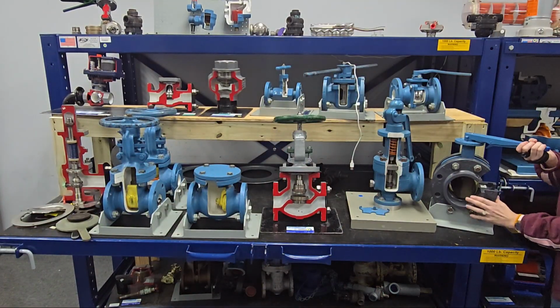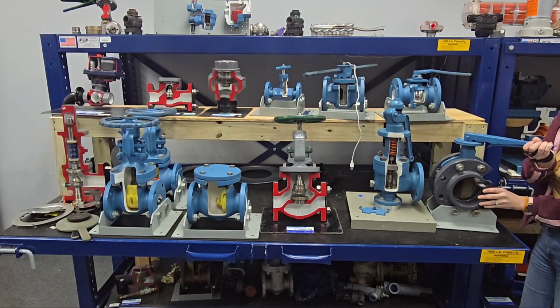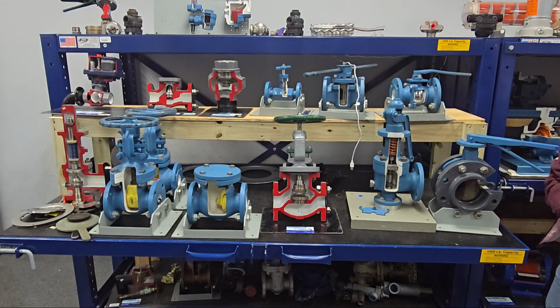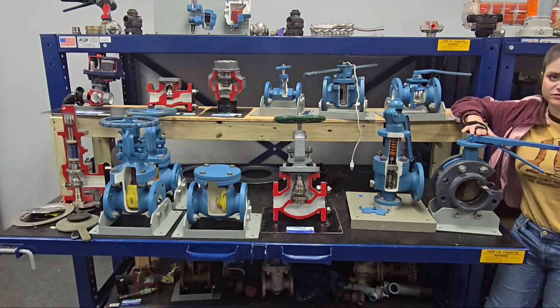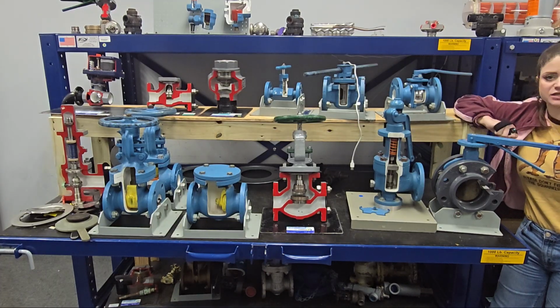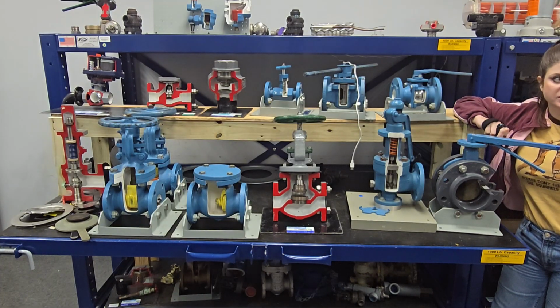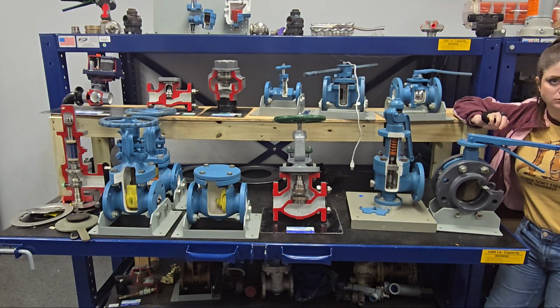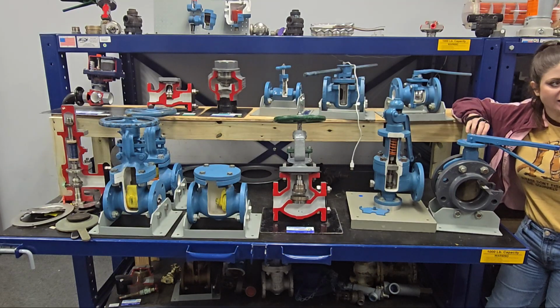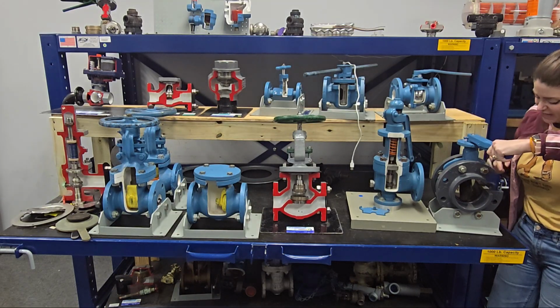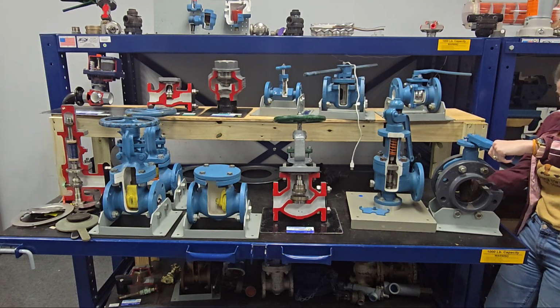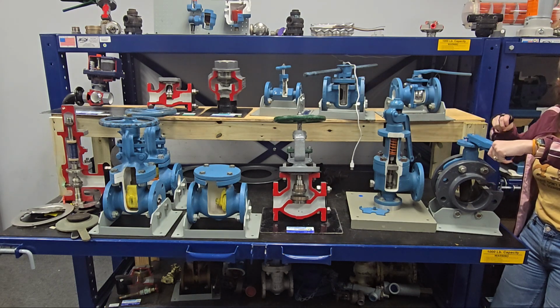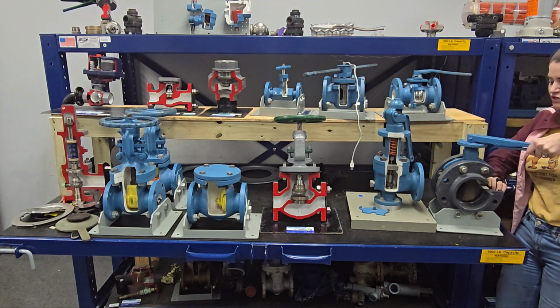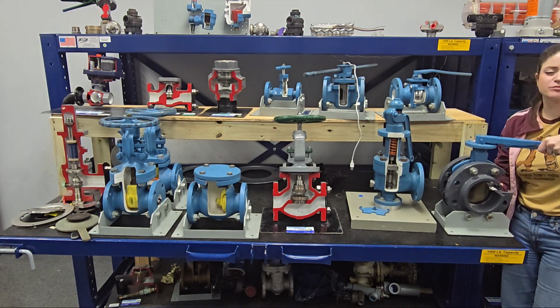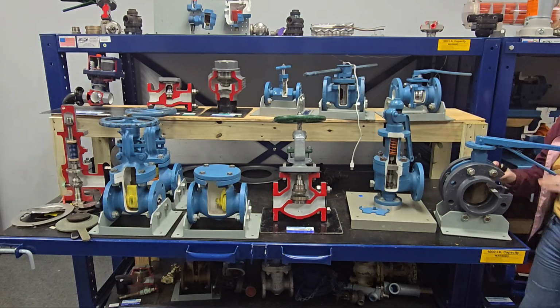What's this one? Butterfly, looks like it has wings, right? Yes. It can be throttled, but what's the negative about having butterfly valves and using them as isolation points? They leak, they're the most likely to pass. Look at how much of a seat it has all the way around the internal of the equipment. So if anything's in there, when you go to close it, it gets trapped. They're the most likely to leak.